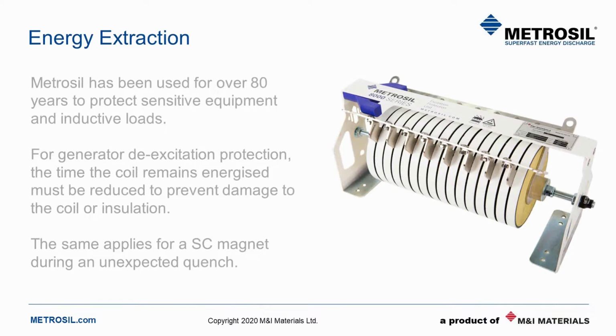As mentioned, from its beginnings METROSIL saw use as an effective and robust overvoltage protection and energy extraction device. For large salient pole generators, you'll find METROSIL switched in across the field windings under de-excitation, clamping the back EMF L di/dt and extracting the energy, protecting the coils of these very expensive machines.